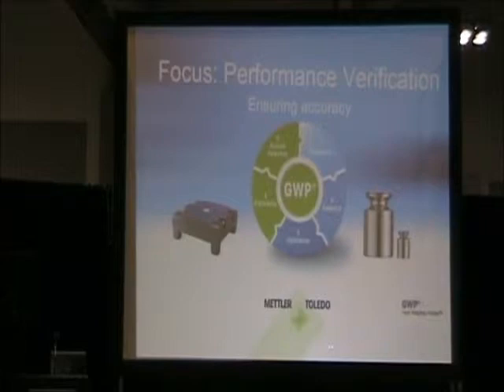Alright, so we're going to now talk about performance verification on your instrumentation to ensure accuracy. There are 3 different portions when it comes to ensuring accuracy on your weighing instrumentation. You have routine testing, which is performed by the end user. You have calibration, which is performed by a service technician normally. And you have what I'm going to call FACT, which stands for Fully Automatic Calibration Technology, which is the operational testing that is done internally on your instruments.